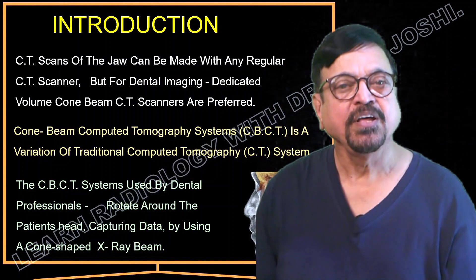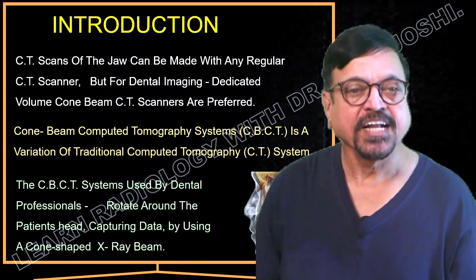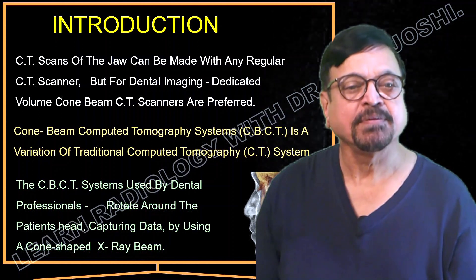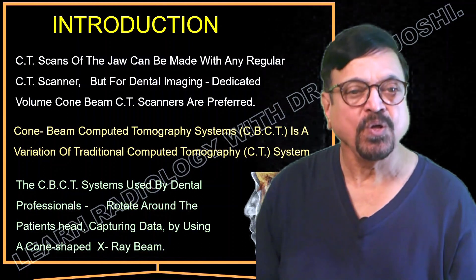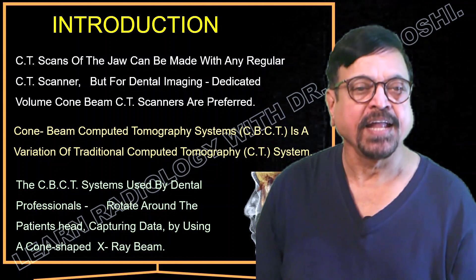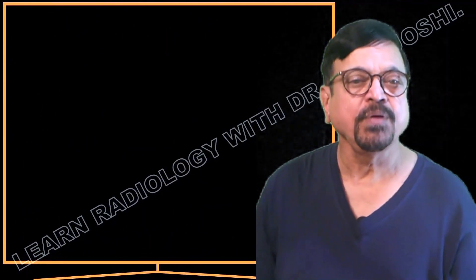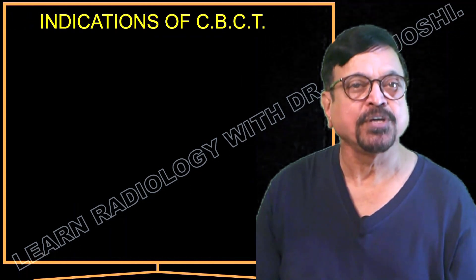The CBCT system used by dental professionals rotates around the patient's head, capturing data using a cone-shaped X-ray beam. It is a modified version of an OPG machine — in OPG there is a film on one side and an X-ray tube on the other side that rotates around the head. Similarly, CBCT is a volumetric machine and gives more volume information than an OPG machine, as it is exclusively designed for that purpose.